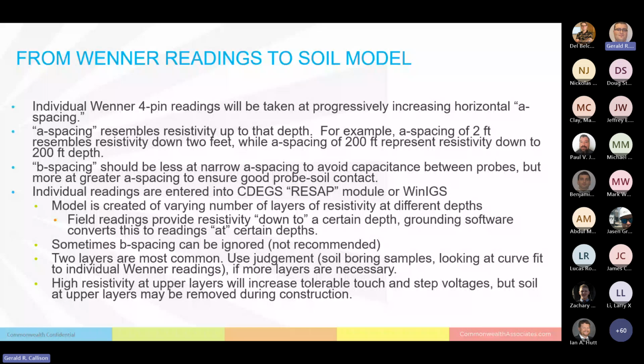So, that's one of the important things that grounding software does. Sometimes grounding software will ignore the depth. We don't recommend that. Again, we'll talk more about that later. A lot of times, 2 layers of soil are going to be enough to represent your soil: resistivity down to a certain depth, and then a resistivity below that.